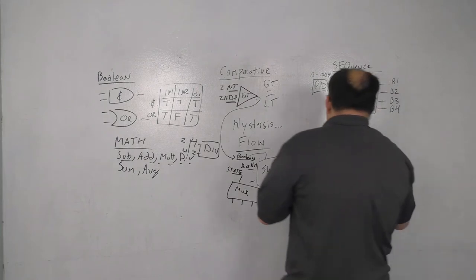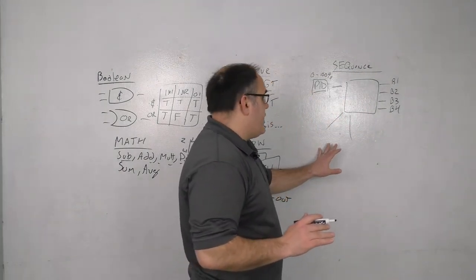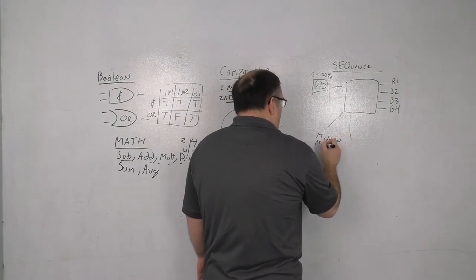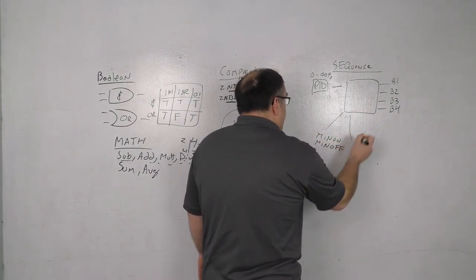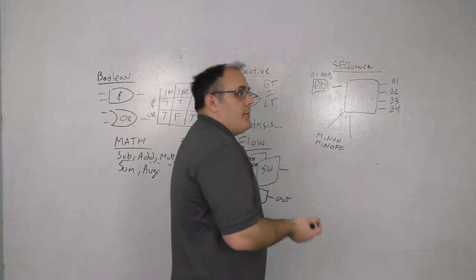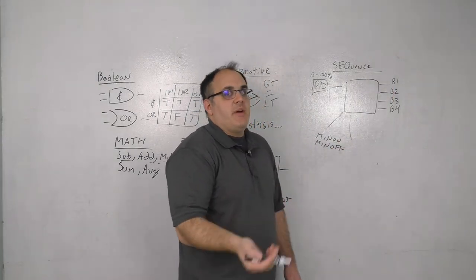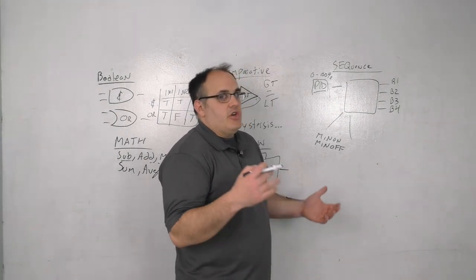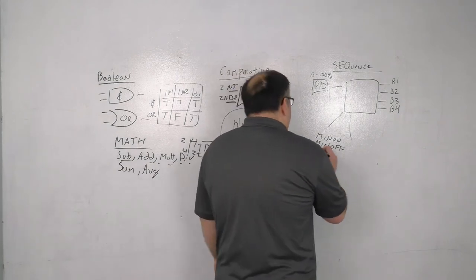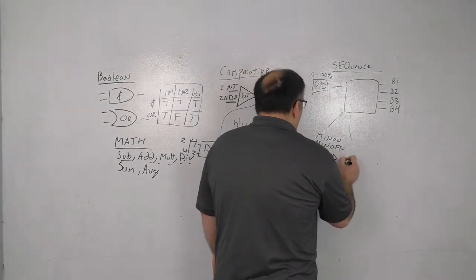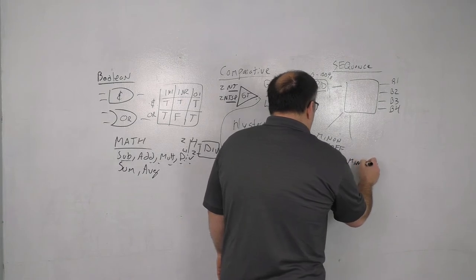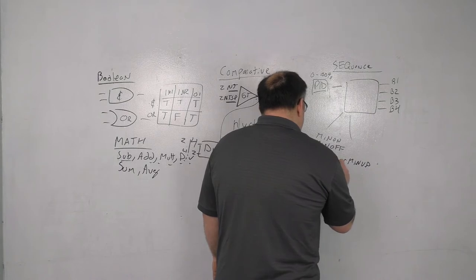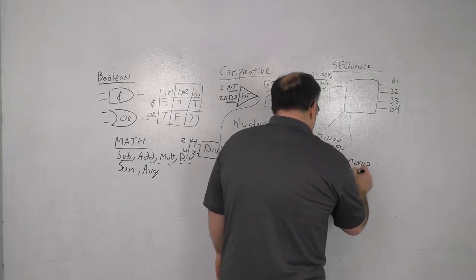And this confuses the heck out of new programmers, all right? So these variables, you've got min on, min off. For each stage, you have a min on, min off time, typically. This is especially true when you're staging on heat, staging on compressors, staging on chillers, etc. And then you have a min load, or what I like to call a min up, and then a min unload, or a min down.